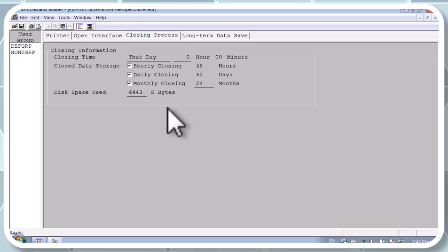Process records the trend data and creates the statistical reports. Instead of storing every sample, it calculates the hourly average, daily average, monthly average, and total value, and maximum and minimum value. For example, we can measure the temperature every second, or after 1 hour the system stores an average of, for example, 25.4.